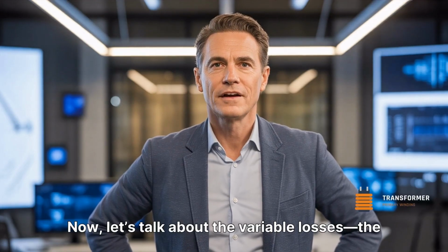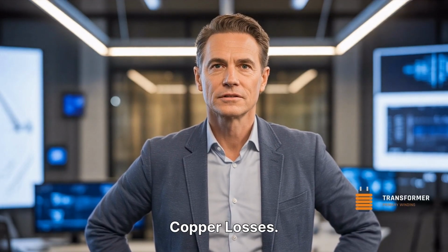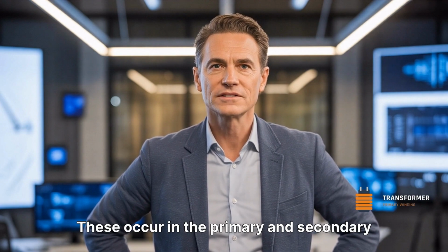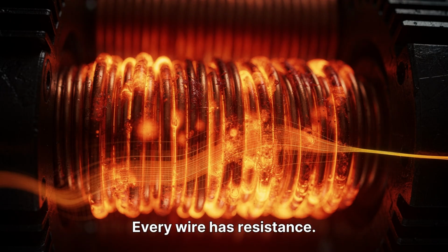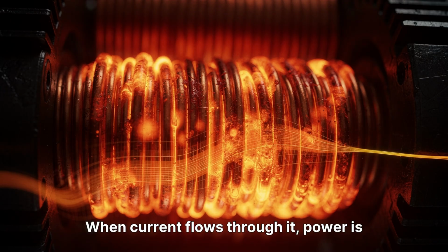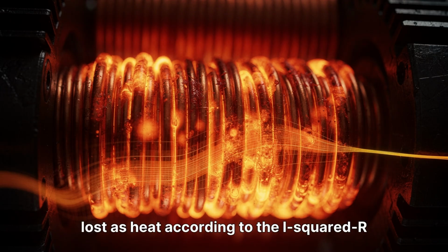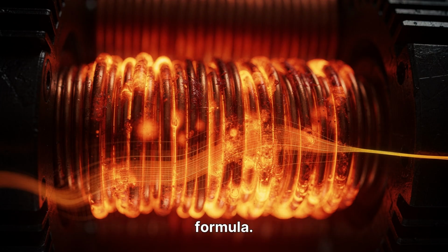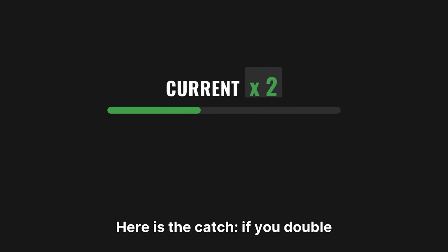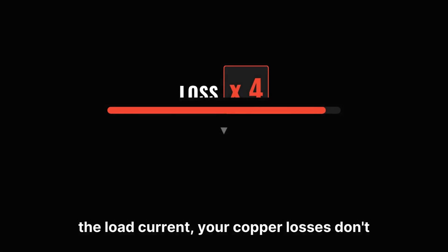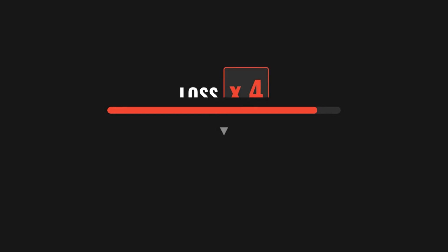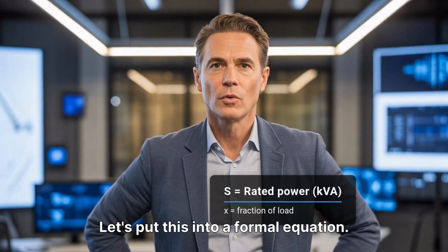Now let's talk about the variable losses, the copper losses. These occur in the primary and secondary windings. Every wire has resistance. When current flows through it, power is lost as heat according to the I²R formula. Here is the catch. If you double the load current, your copper losses don't double. They quadruple.